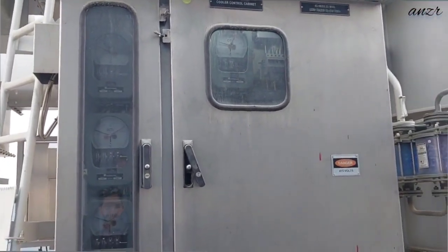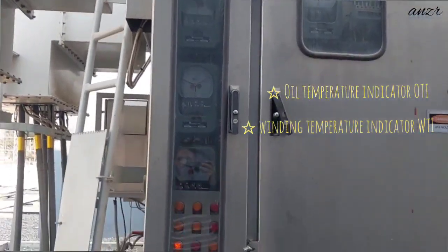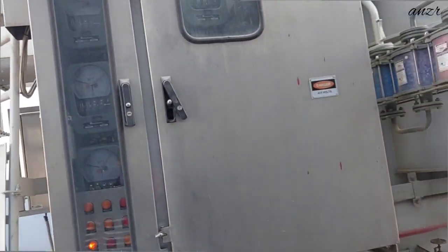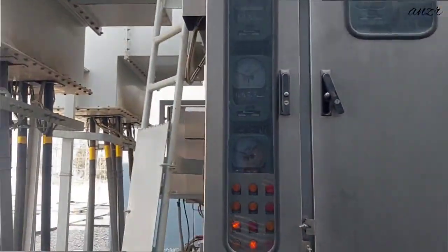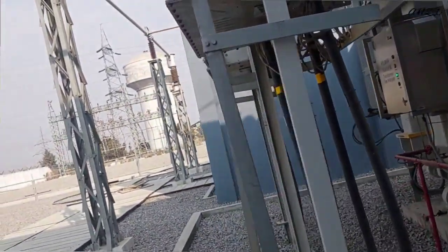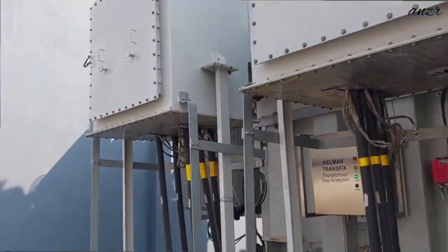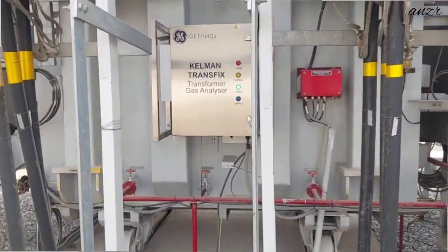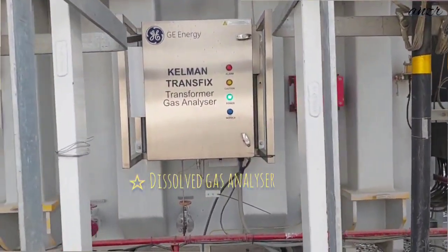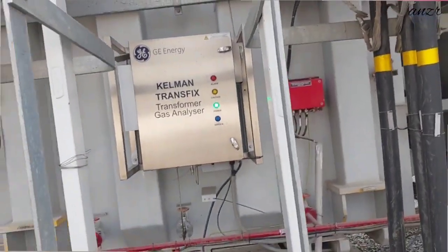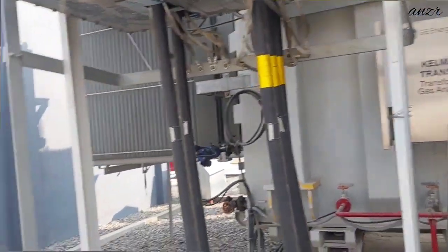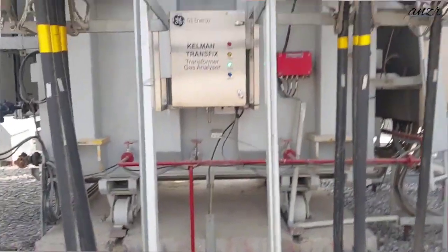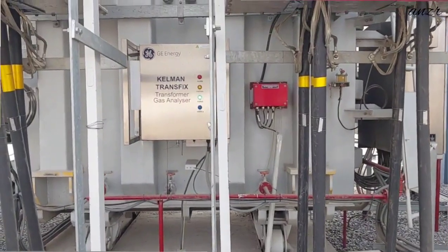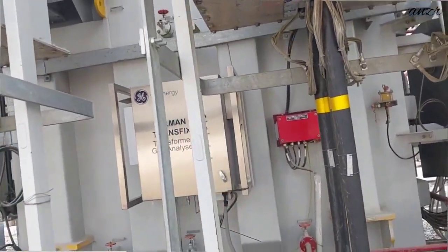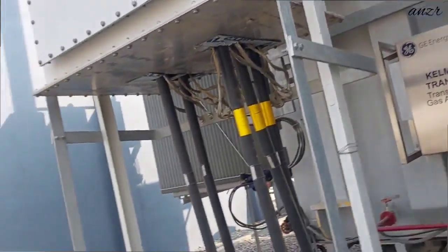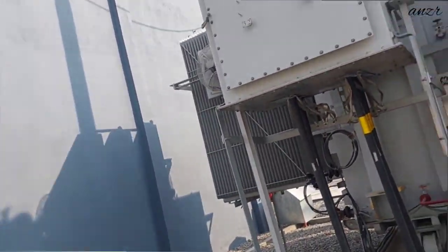Here you have different meters, oil temperature indicator, winding temperature indicator units. They show the oil and winding temperatures. So in case there is a high temperature, the respective relay will get pushed and will turn off this system. So here you have a Kelman Transfix transformer gas analyzer. So this is a gas analyzer from GE Energy. So this analyzes the internal gases and checks where from these gases are coming. So it helps us in fault detection, early fault detection. If there is some uneven type of gas present inside this system, it may indicate from where that gas is coming, and it may give us an early indication of where the defect lies.